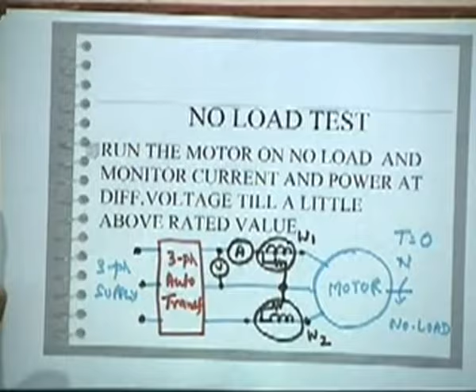Now the other test, blocked rotor test, is also a zero power output test, because you are maintaining the speed 0 but torque is there, so that is also zero output power. Today we will have another zero output power test, which you call a no load test, in which case you are maintaining the torque 0 at the output but speed is there. So that is the other test that we conduct on the motor to determine its parameters and certain losses, that we will see today.